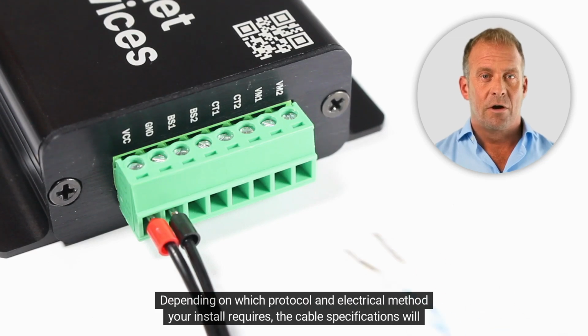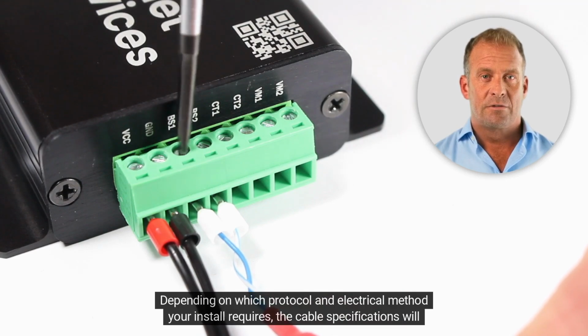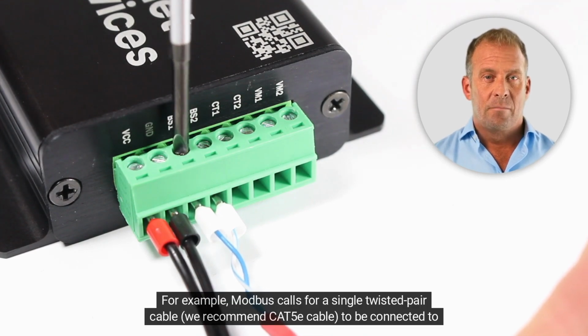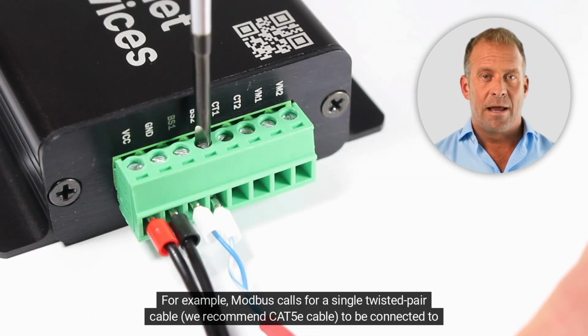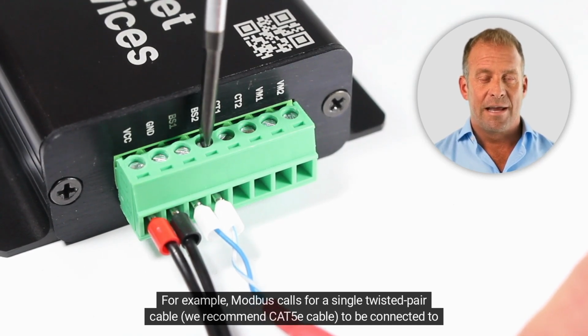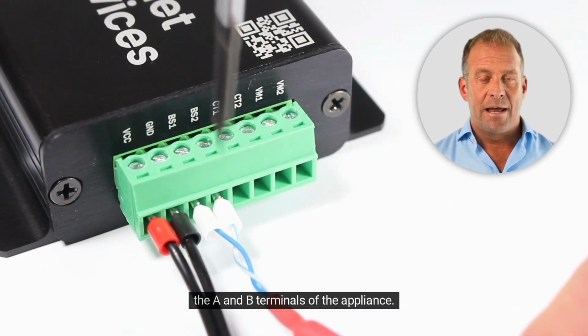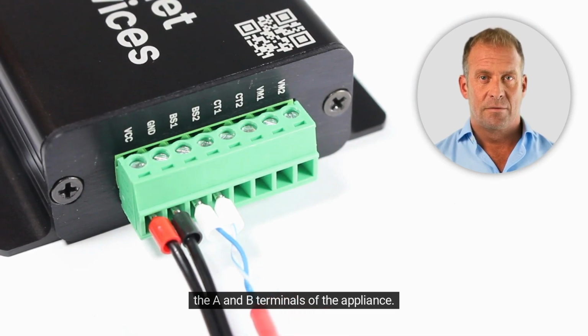Depending on which protocol and electrical method your install requires, the cable specifications will differ. For example, Modbus calls for a single twisted pair cable. We recommend Cat5e cable to be connected to the A and B terminals of the appliance.